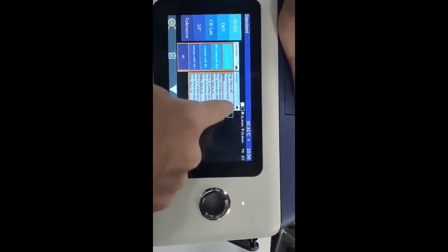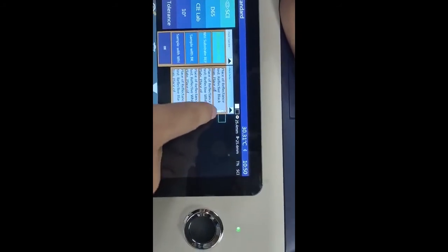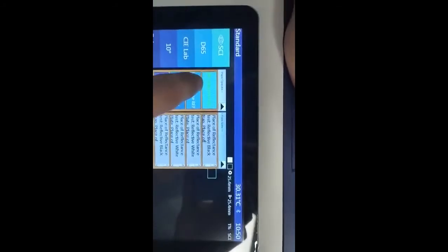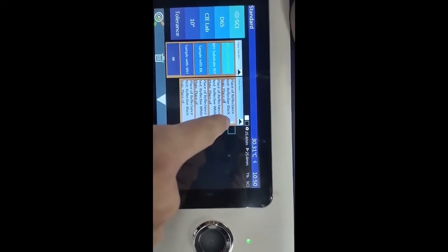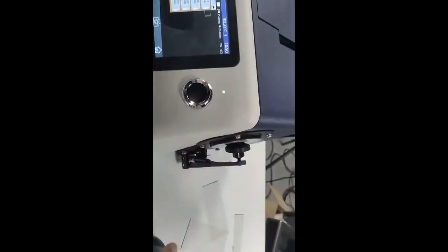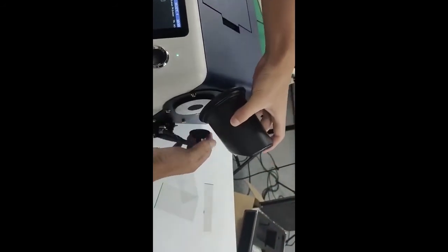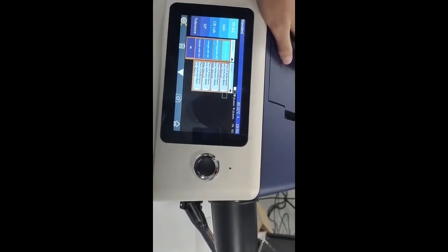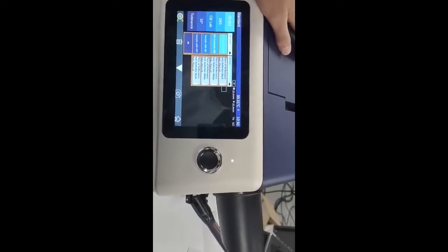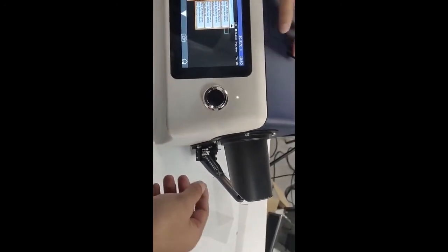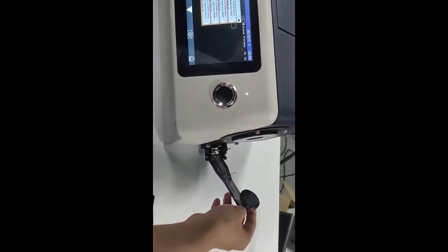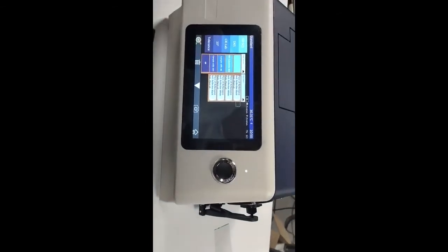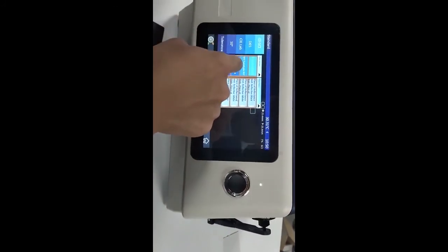Pay attention to the prompt here. Mirror haze is kind of complex. First, black substrate reference. We put the black cavity at the reflectance measurement position and touch here. And then second, white substrate reference.